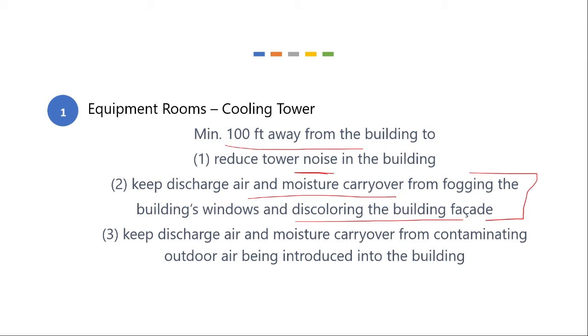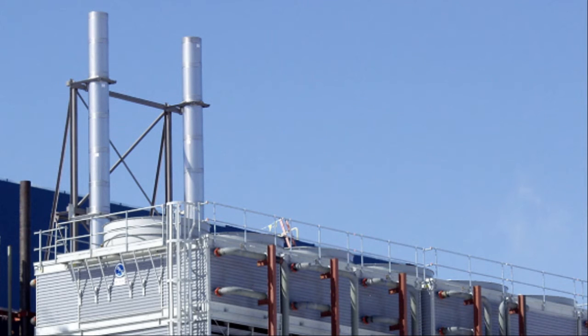You also want to keep discharge air from contaminating the outdoor air. Otherwise, what you end up with is you have a building and you have an air intake and you have a cooling tower, and the dirty air just flows back into the building, and that doesn't do you any good. So here's an example of a cooling tower.